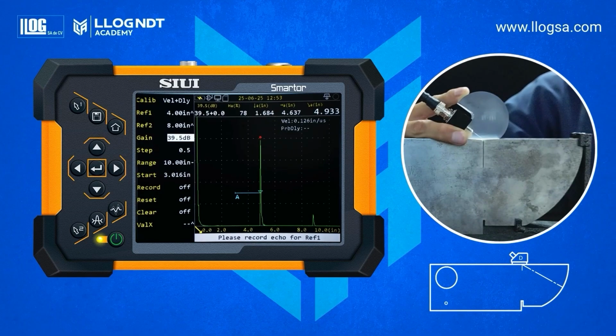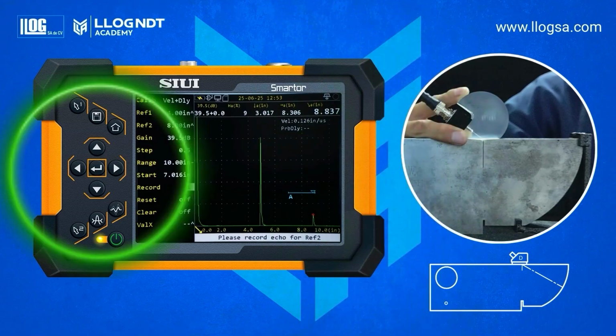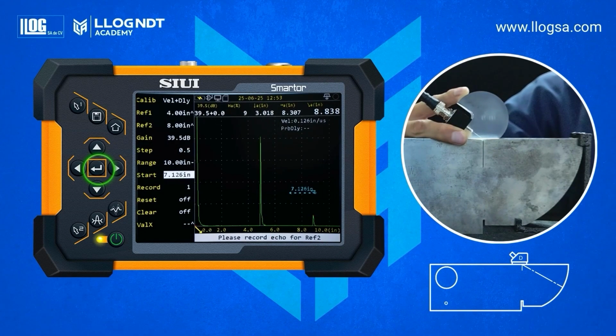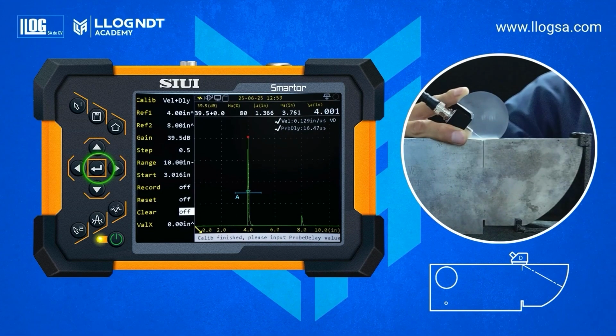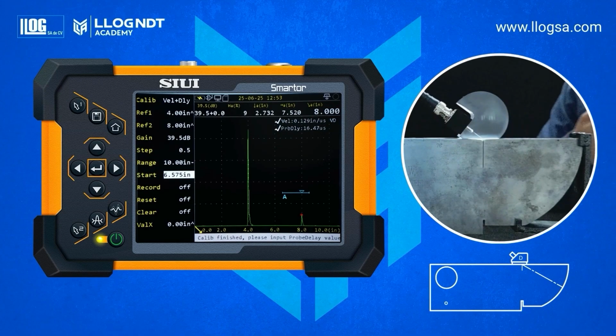In that same position, press Enter on the record function to store the first reference at 4 inches, and then the second reference at 8 inches. Once the calibration is complete, verify that the measured distances are 4 inches and 8 inches. With these steps, we have completed the distance calibration.